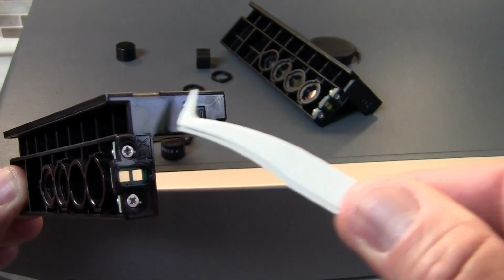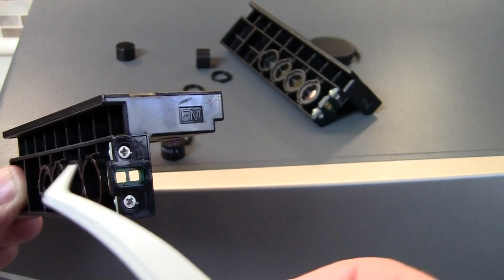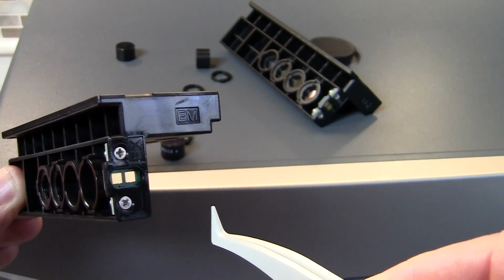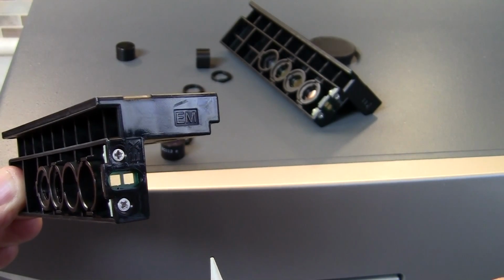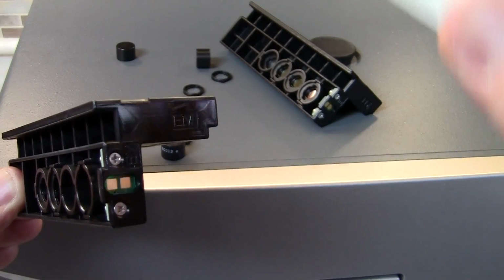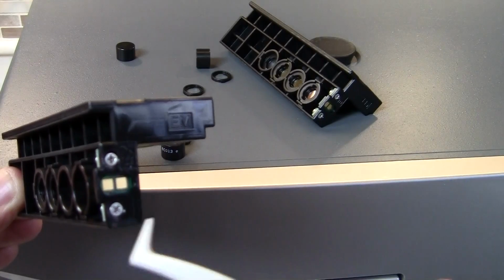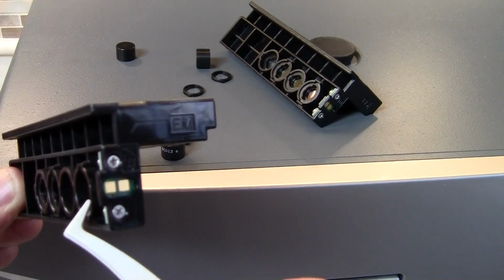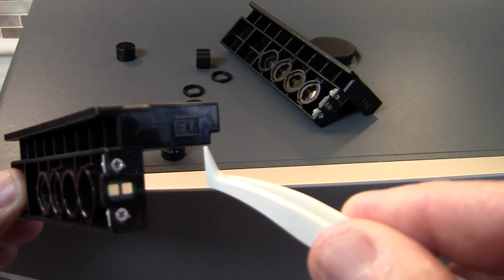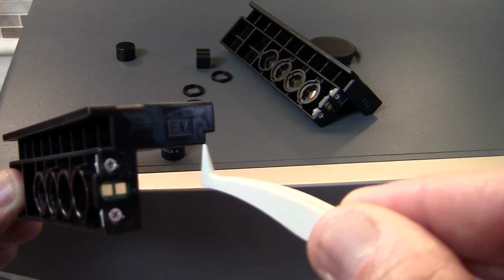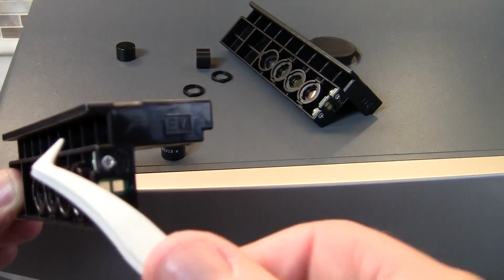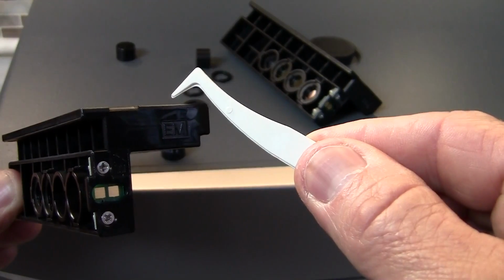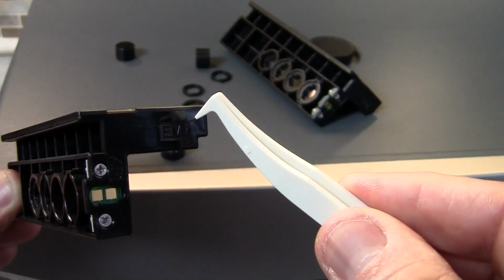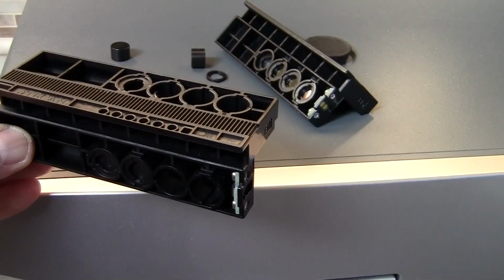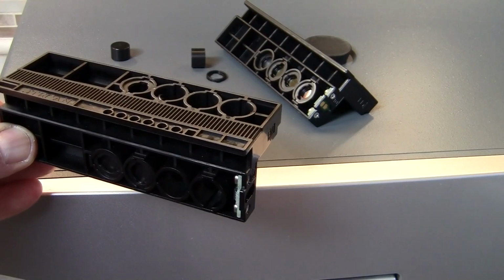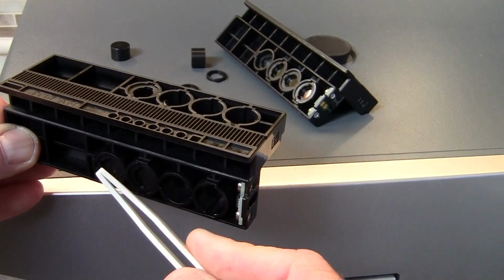In the case of this particular holder, light travels from left to right, and then eventually, if there is fluorescence being detected, light is going to be transmitted up and through this particular emission filter section. Therefore, for filters placed on this side, the excitation side, the arrows must point inward, and for filters placed in the emission side, the arrows should point up. Another way to say this is that the top side of the filter should face out here, and the top side of the filter should be placed in headfirst into this particular side of the holder. Filter positions on the holders are numbered 1 through 4, with this position being number 1, 2, 3, and 4.